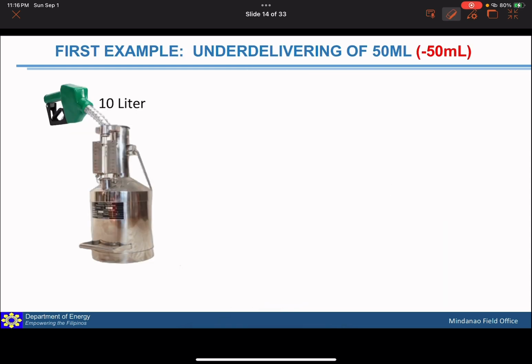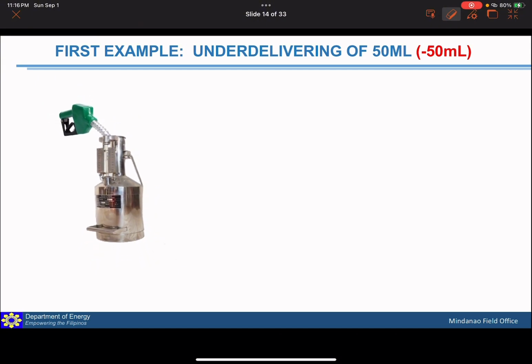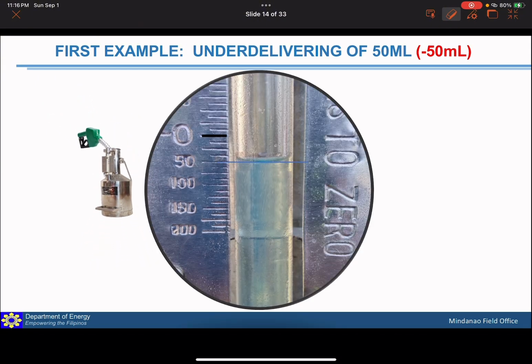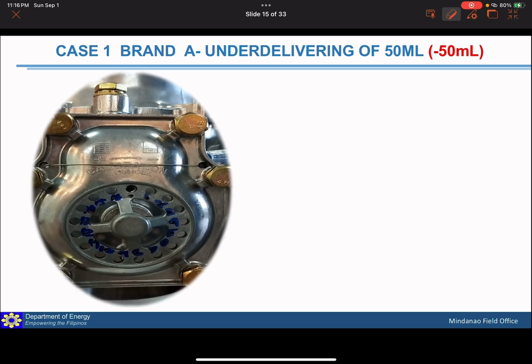Okay, let's have an example. So, we dispense 10 liters sa calibrating bucket. Then, ang resulting reading is negative 50 ml. Though it is still in the maximum permissible error, we still need to return it back to zero. So gagawin natin is we will adjust the calibration sa mechanical wheel because we are only focusing on the mechanical calibration. For this type of meter, ang naka-engrave is plus is counterclockwise and minus is clockwise.